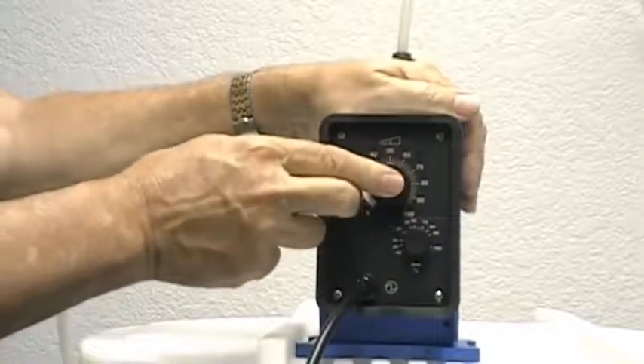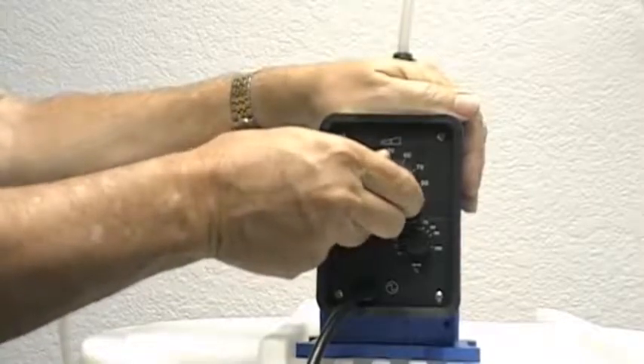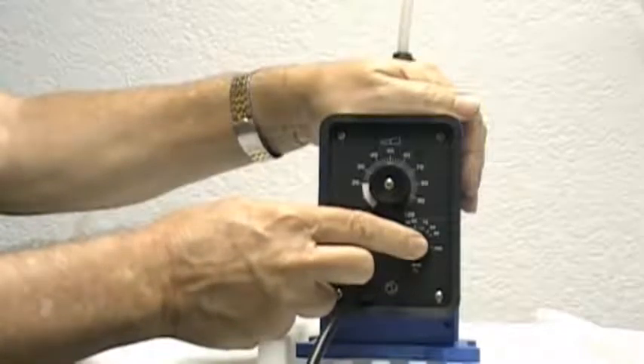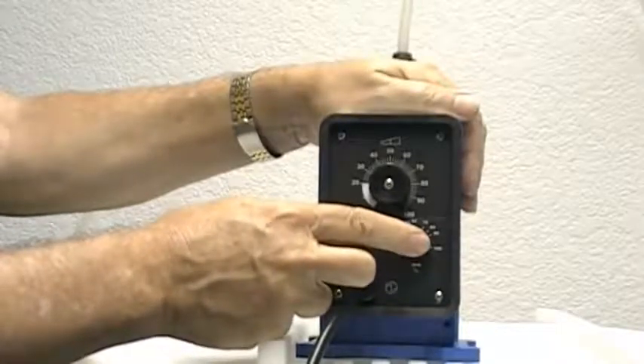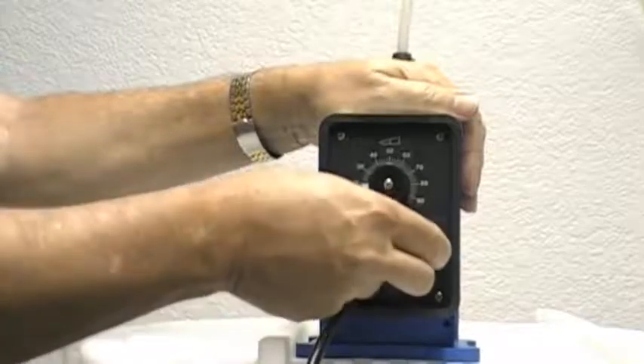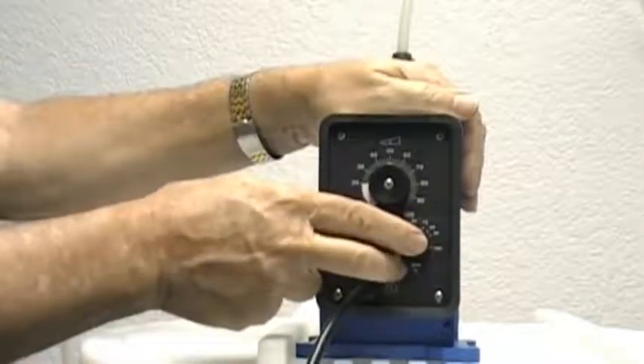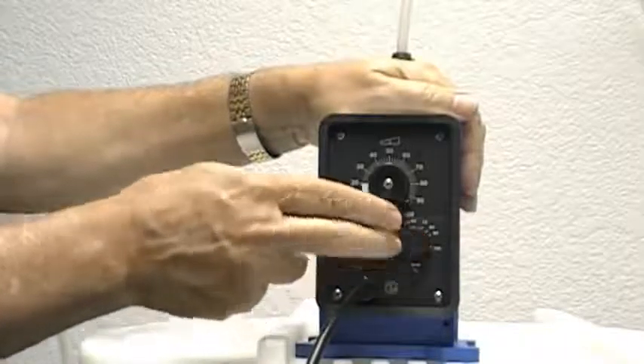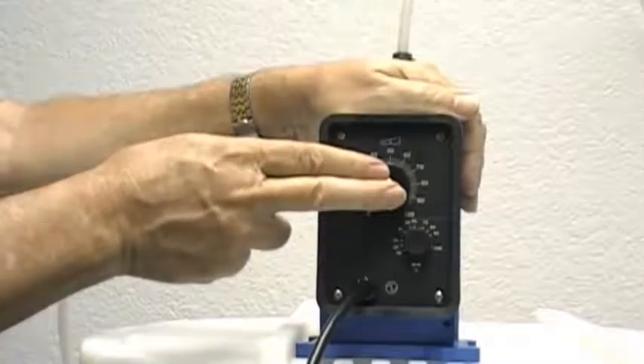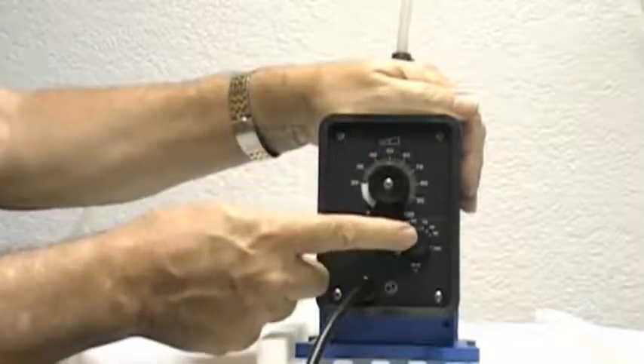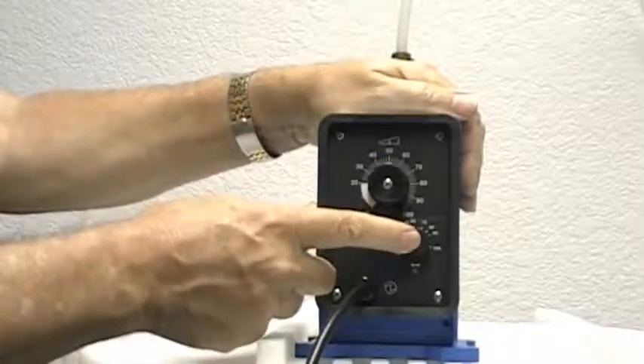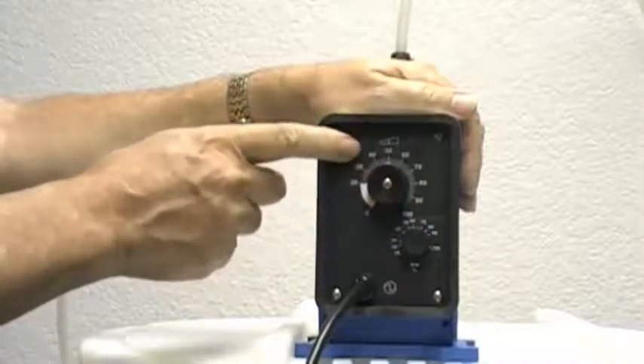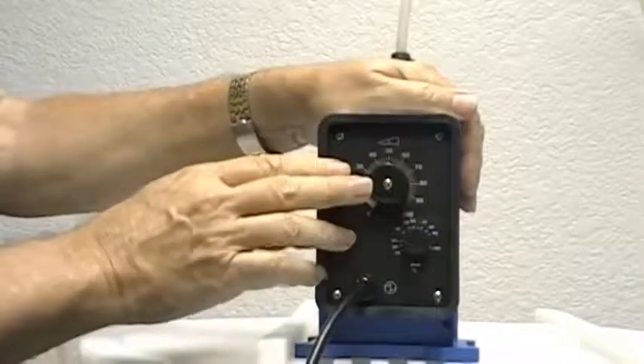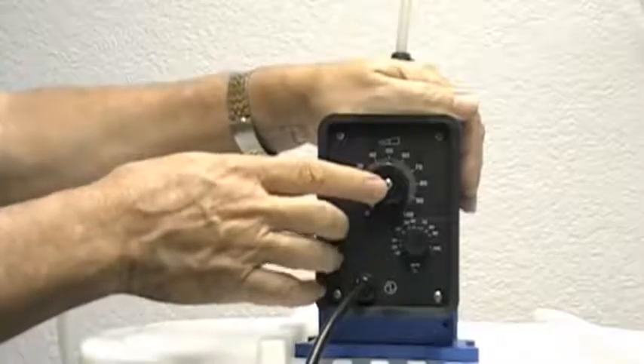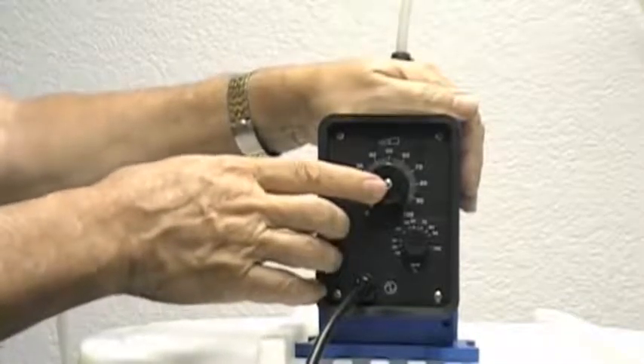The stroke length adjustment adjusts the amount of flow per stroke. The stroke rate adjustment adjusts the number of strokes per minute. At 100%, there would be 125 strokes per minute. As an example, for a 6-gallon-a-day pump with the stroke rate adjustment at 50%, there would be 3 gallons per day produced by the pump. If we adjust the stroke length to 50%, then that will reduce the flow rate to 1.5 gallons per day.